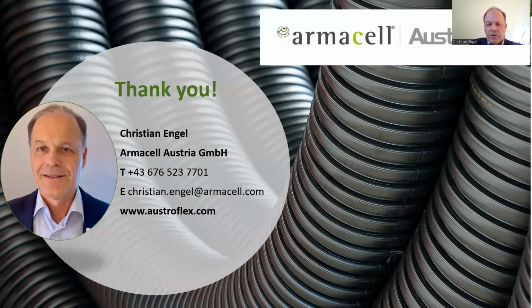We have one network where they didn't control it and went up to 90, 95 or even above, and after 30 years they had a few problems. So it's really imperative, and Magnus has shown that very clearly, that permanent control in different ways, and developing these measures further to permanently control the network and look for possible improvements over the years, is key for a long lifetime.